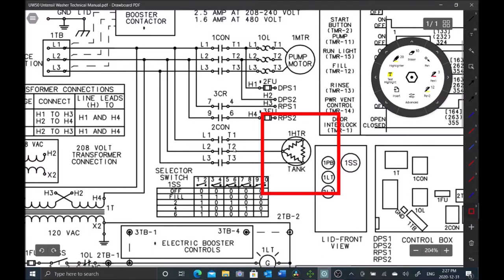Finally L3 is right here coming through the contacts and that's going directly to our terminal block. As we can see there these contacts are not closing. We had that visual cue. So the next step now is what closes the contacts.